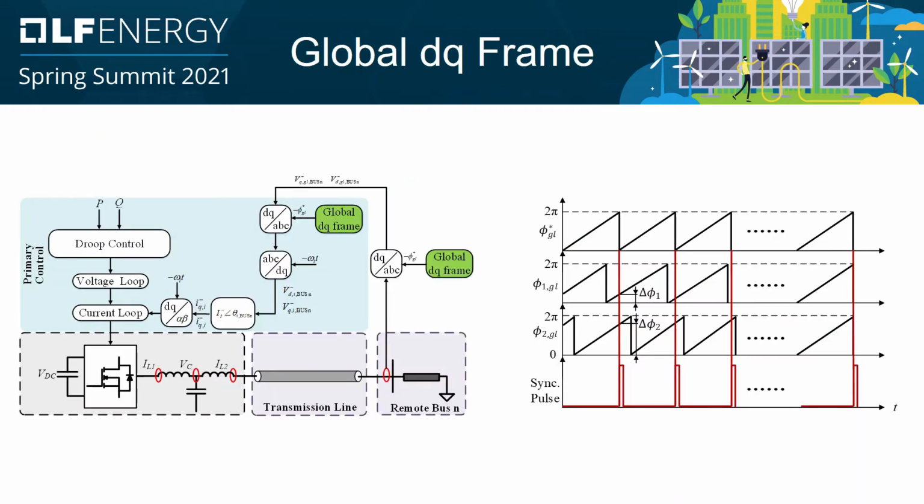A potential problem in microgrids with multiple generators is voltage unbalance. A typical solution is for one generator to compensate voltage unbalance by injecting negative sequence current in phase with negative sequence voltage. The issue is that the local generator controller must have a direct sensor connection to the compensated bus to measure instantaneous three-phase voltage. But physical distance can cause delays and negate the compensation effects.